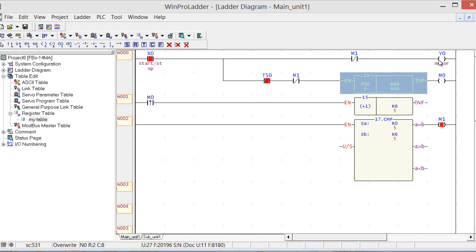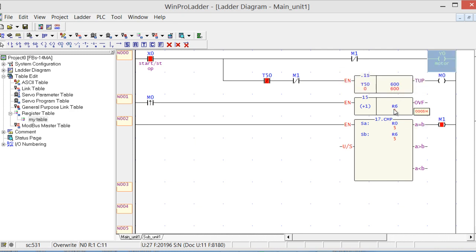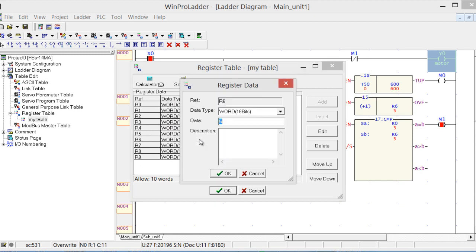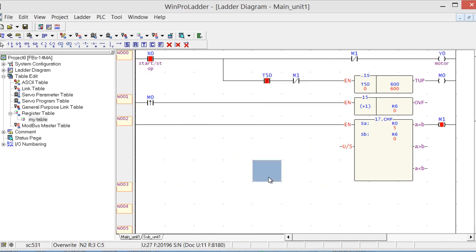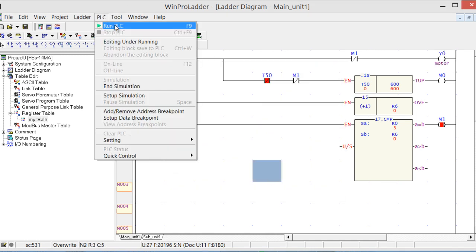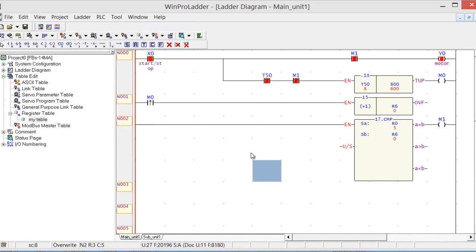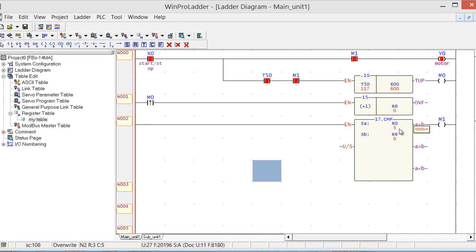Now how it works: keep Y0 on for 5 minutes, because now R6 will increment after every 1 minute. Let's change this value, make it 0. Run the PLC. You can see that it will increment R6 exactly after every 1 minute, so when 5 minutes will be completed, it will turn off this motor.